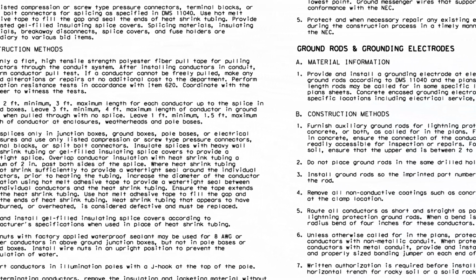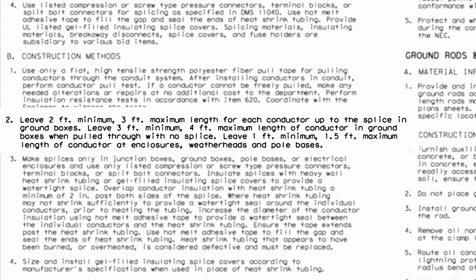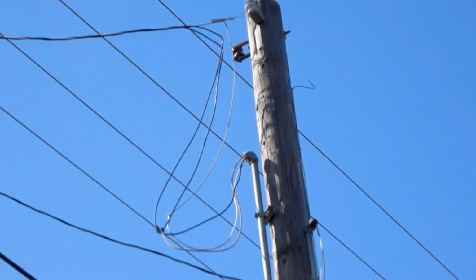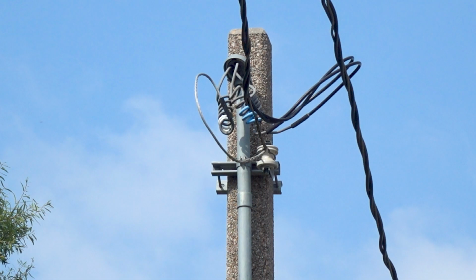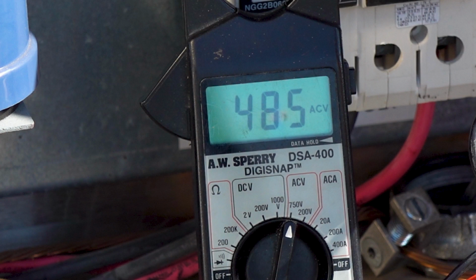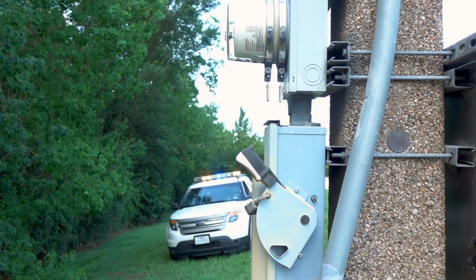In ED3B, Construction Methods, Note 2, specifies that the service entrance conductors be between 12 and 18 inches in length, as measured from where they exit the weatherhead. These conductors should be routed so that they do not touch the service support structure at any point other than an insulated wiring device. If contact is made with the support structure, over time, the conductor's insulation can be damaged, and a ground fault could cause the main breaker of the service to trip. When the supply voltage is 480 volts, the serving utility may require that a switch be installed just before the electric meter.